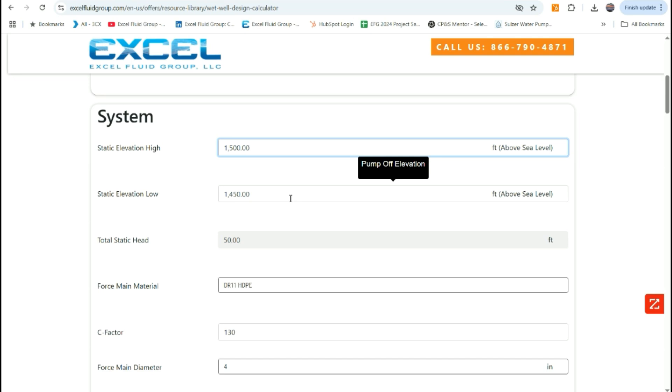What you'll need is the static elevation high point in the force main, or if that's the discharge point into a sanitary manhole, and then the static elevation low point, which typically would be the pump off elevation in the wet well. These values can be found typically on a force main profile drawing. That will calculate your static head.